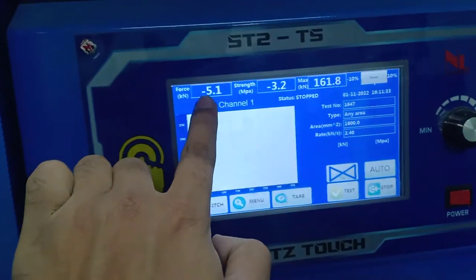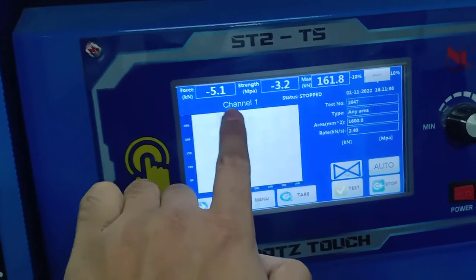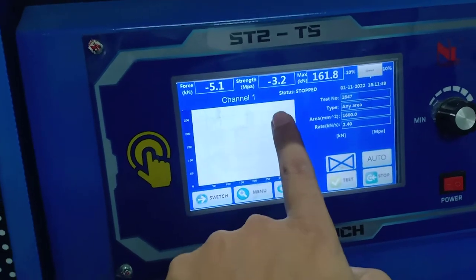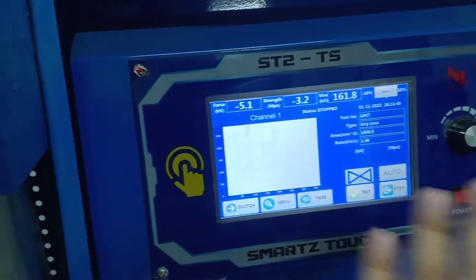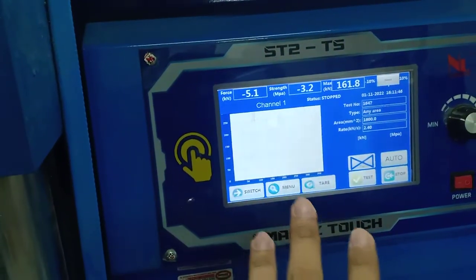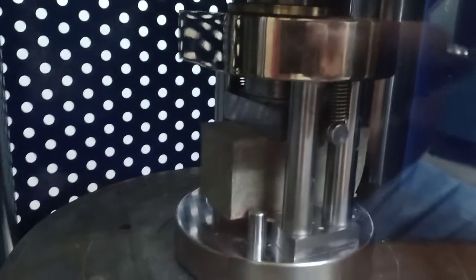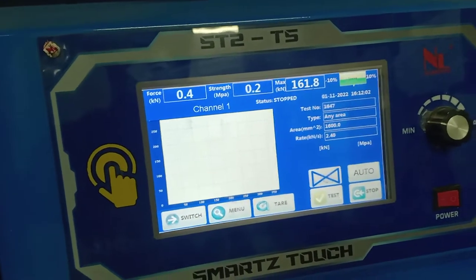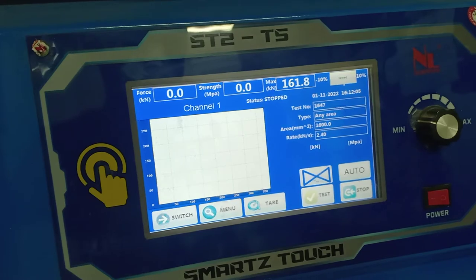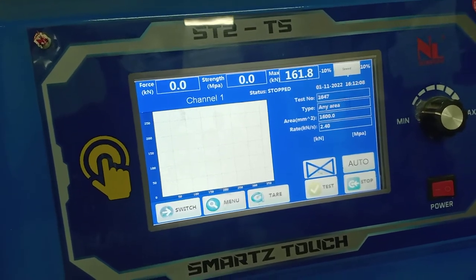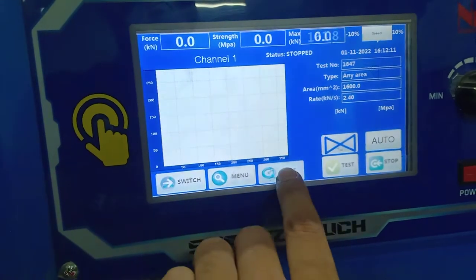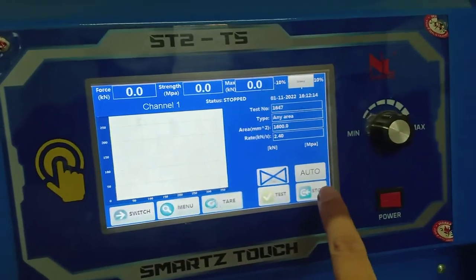I check the display — it still shows minus 5.1 for force and minus 3.2 for the other channel. I need to make sure this reads 0 or a positive value. Once it reaches 0, I confirm it is zeroed, then I press tare to reset. Now it is set to auto, and I start the test.